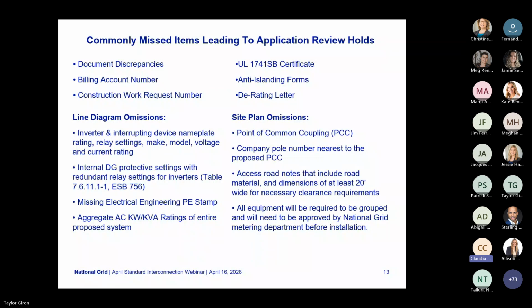In this slide, we have outlined some of the most common issues that we have seen as the screening team reviewing these applications. Most missed items are, for example, document discrepancies. For example, we have an address that is not matching in the application, site plan, line diagram, or legal information document. Other items are a billing account number that is missing or is not completely 9 digits, a construction work request number that has not been requested or is missing, a UL 1741 SB certificate that is required for all projects above 100 kW, and anti-islanding forms not on the most up-to-date forms.